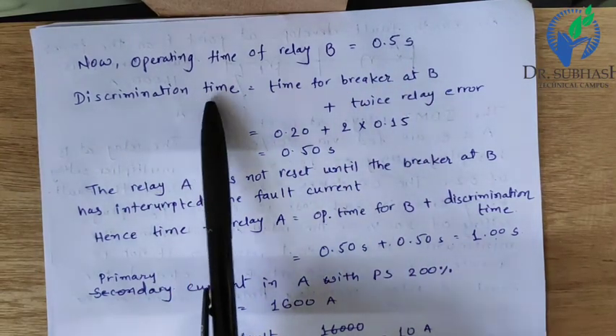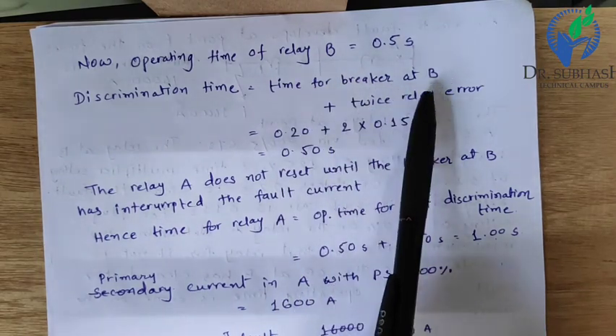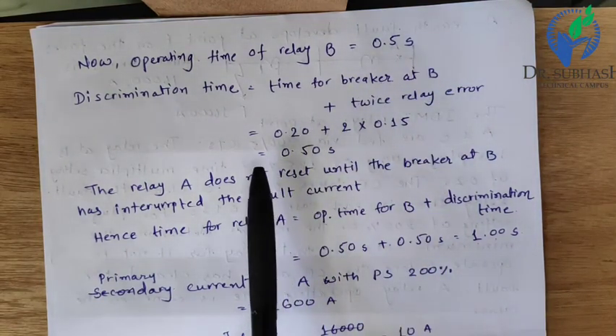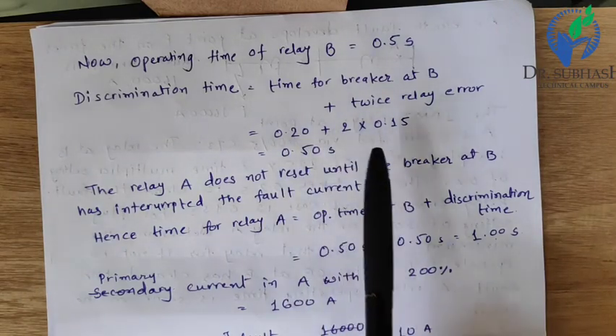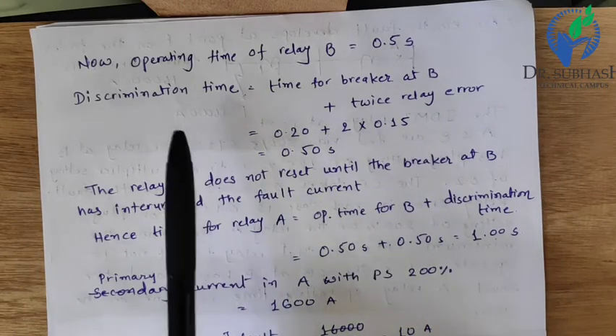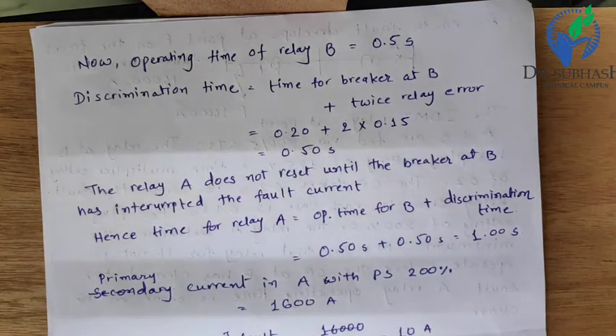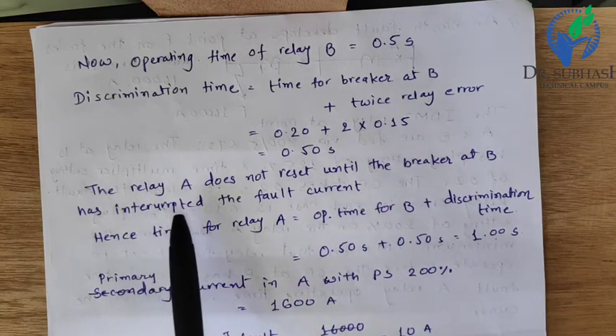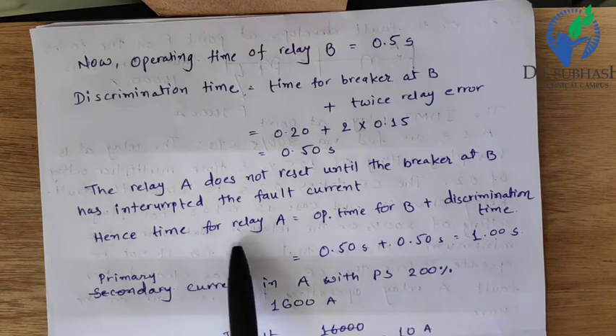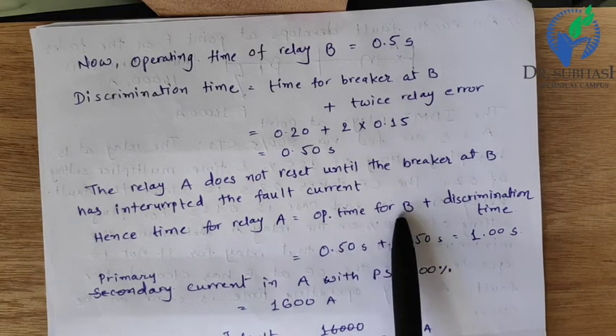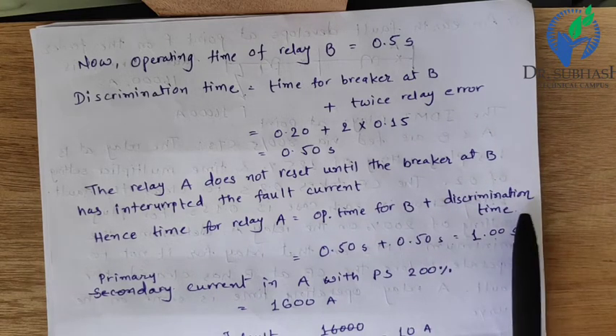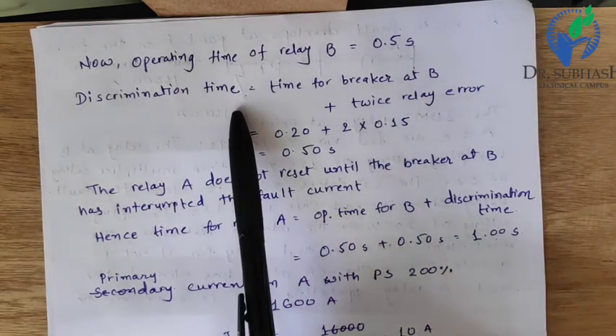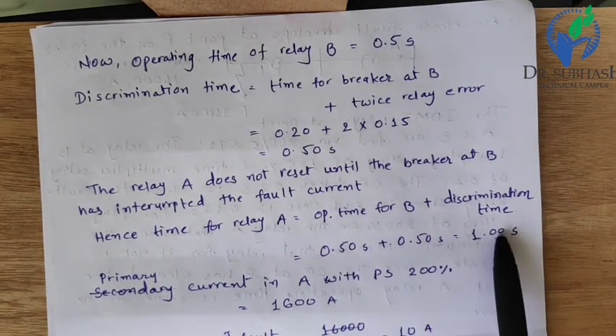Discrimination time equals time for breaker at B plus twice the relay error: 0.2 + (2 × 0.15) = 0.5 seconds. Since relay A does not reset until the breaker at B has interrupted the fault current, the time for relay A equals operating time of B plus discrimination time: 0.5 + 0.5 = 1 second.